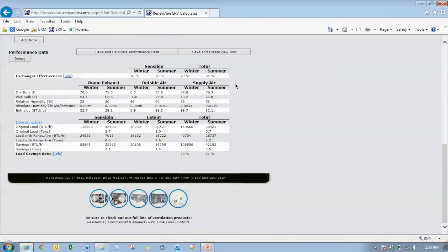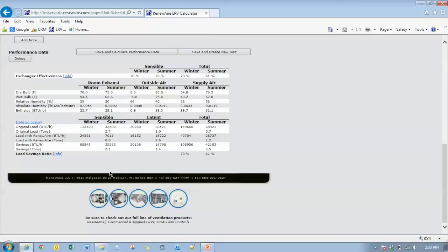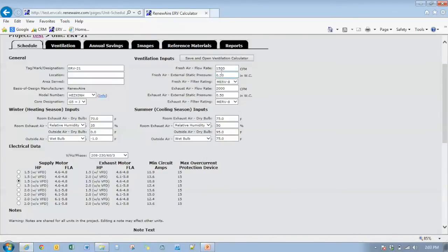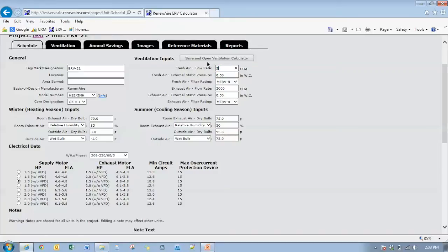And again, you'll see the energy exchanger effectiveness numbers. When we have more exhaust air going out of the building than we have outside air coming in. Again, the exchanger effectiveness numbers are going to match the load savings ratio. It only has an impact when the outside air, the fresh ventilation load is higher than the exhaust air stream. So we'll go back to 1500 CFM.